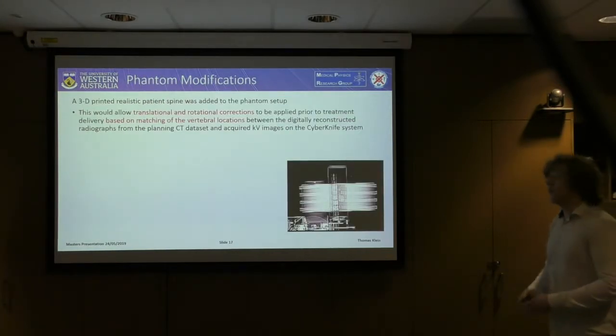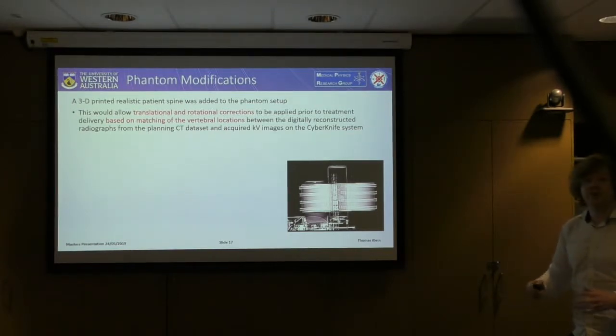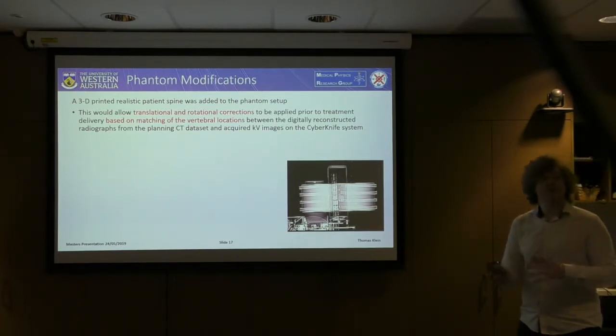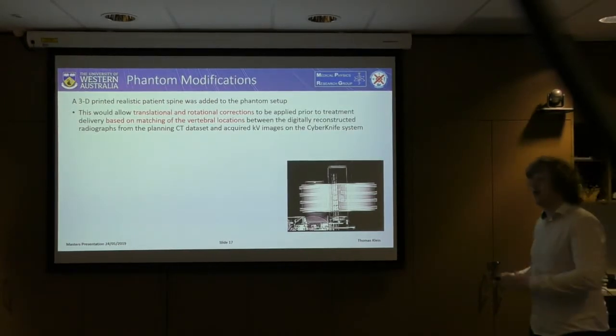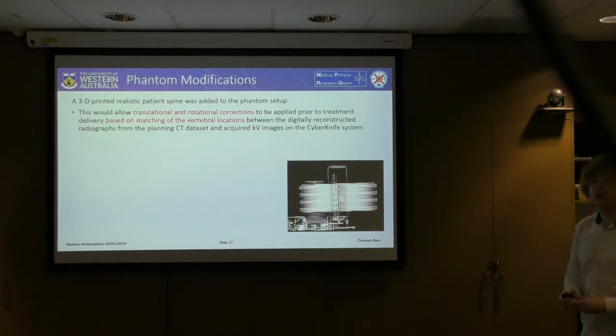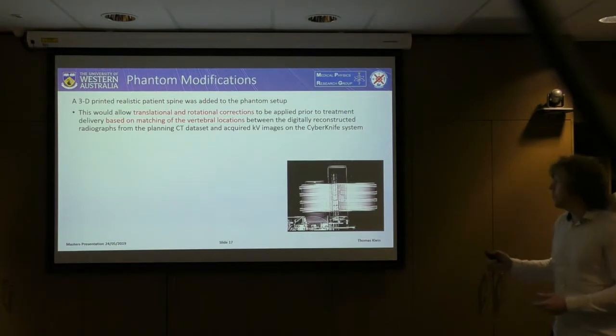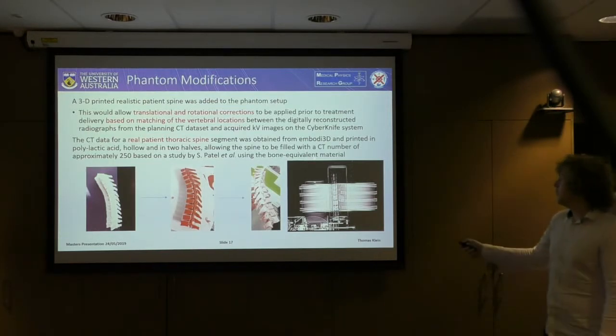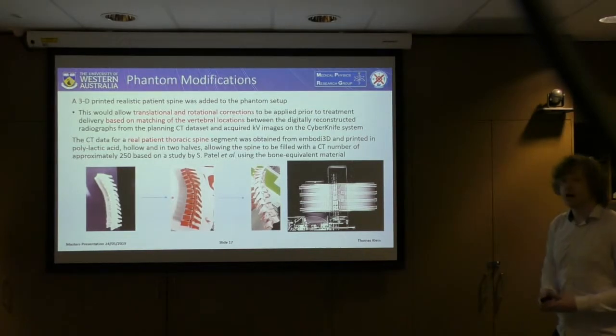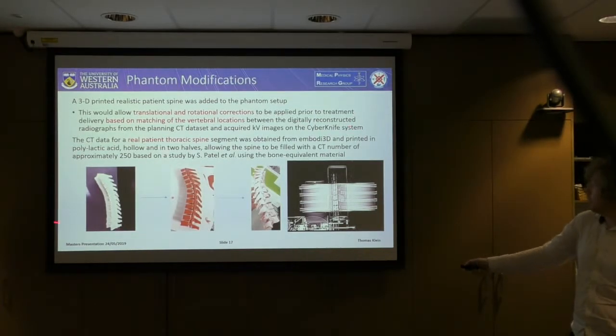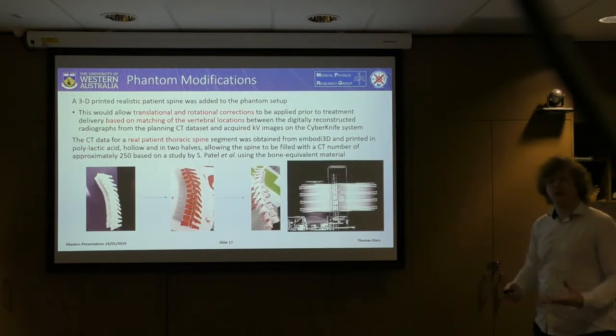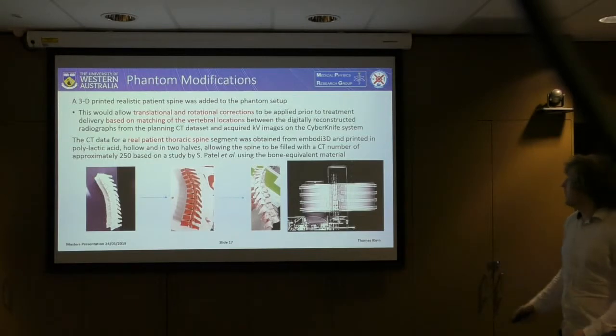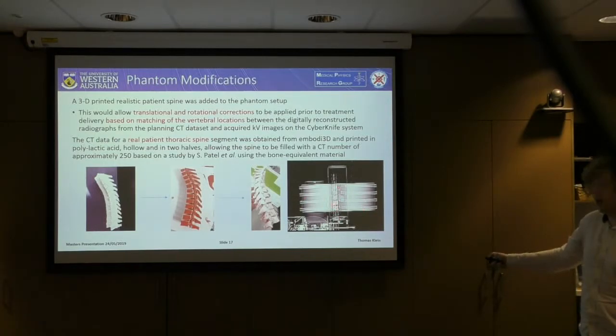Following this, we created a 3D realistic patient spine. This is important because immediately prior to treatment delivery, we can apply translational and rotational corrections to the patient's setup based on rigid matching of bony vertebrae structures in acquired images compared to the CT dataset. We acquired CT data from a real patient's thoracic spine segment from Embody3D, an open-source biomedical 3D printing database, and printed it in polylactic acid — hollow and in two halves — allowing the bone to be filled with our bone-equivalent material at a CT number of approximately 250, based on the study of vertebral densities by S. Patel. The CT scan of our final setup shows the spine lying behind the lung volume.